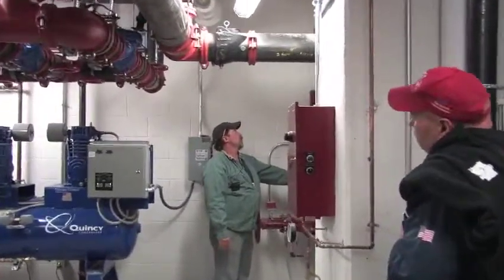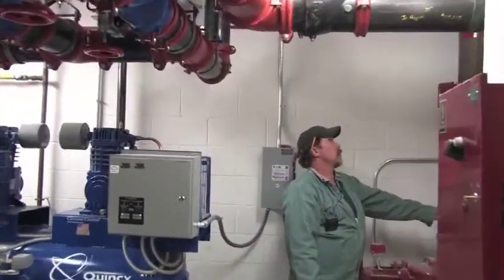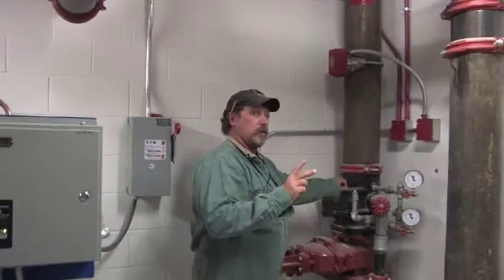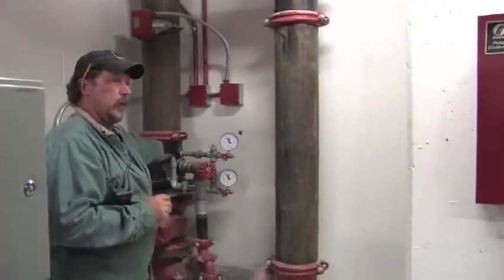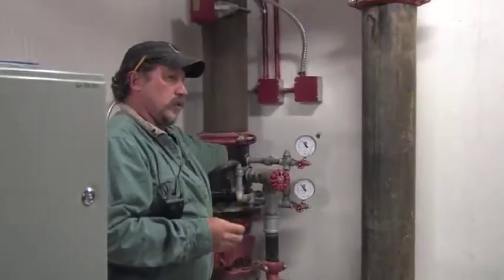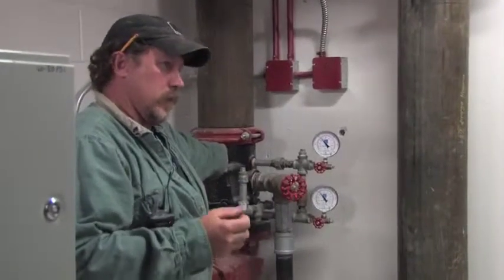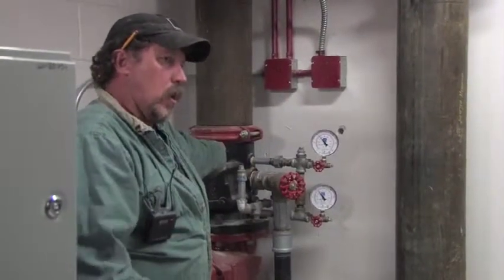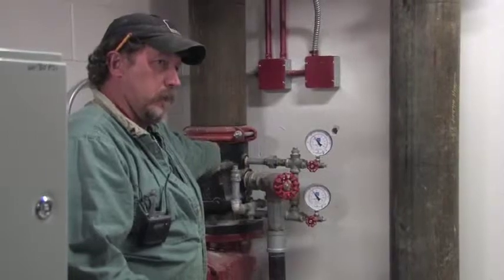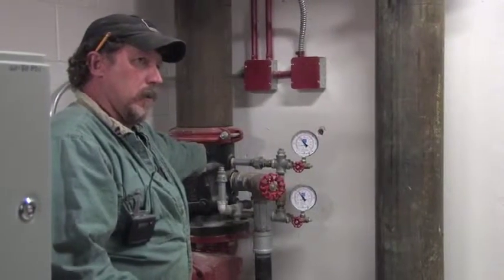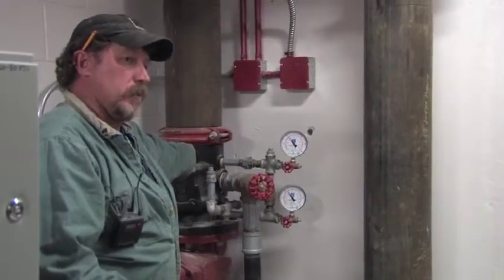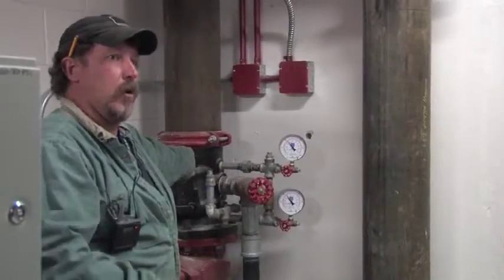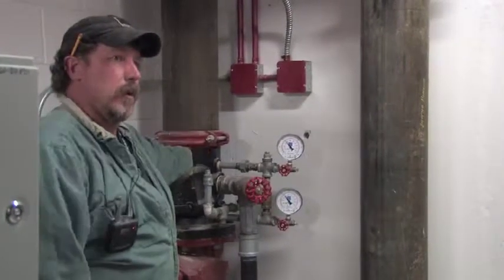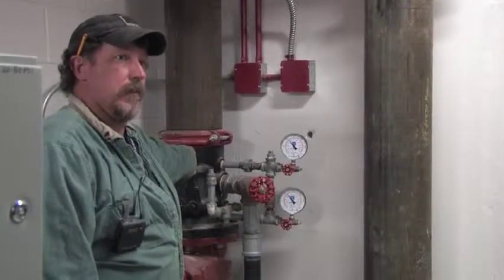This is feeding combination standpipes, the high systems and the low systems. There's going to be two systems in this building. There's a low system, which is going to take care of sub-basement all the way up to the 4th floor mechanical. And then you have the high system. It's going to start on the 6th floor and take you all the way up to the mechanical floor, pretty much on the roof, up to the 11th floor.